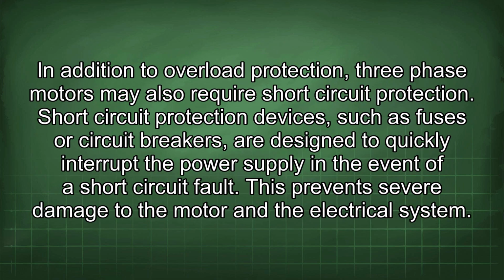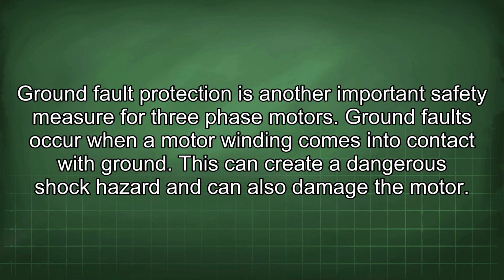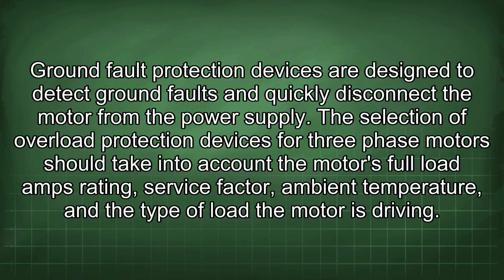In addition to overload protection, three-phase motors may also require short-circuit protection. Short-circuit protection devices, such as fuses or circuit breakers, are designed to quickly interrupt the power supply in the event of a short-circuit fault. This prevents severe damage to the motor and the electrical system. Ground fault protection is another important safety measure for three-phase motors. Ground faults occur when a motor winding comes into contact with ground. This can create a dangerous shock hazard and can also damage the motor. Ground fault protection devices are designed to detect ground faults and quickly disconnect the motor from the power supply.